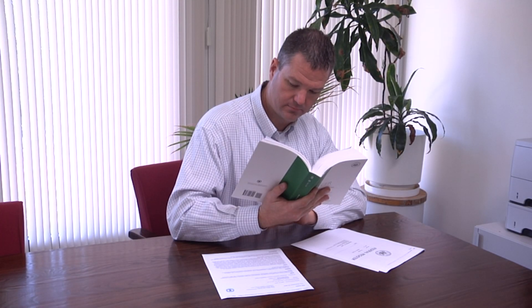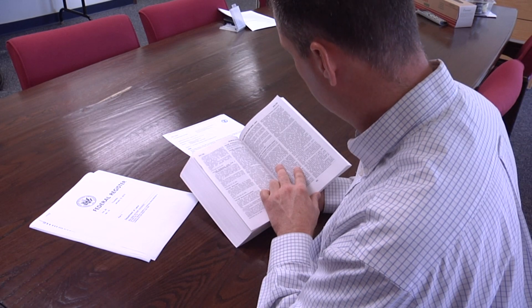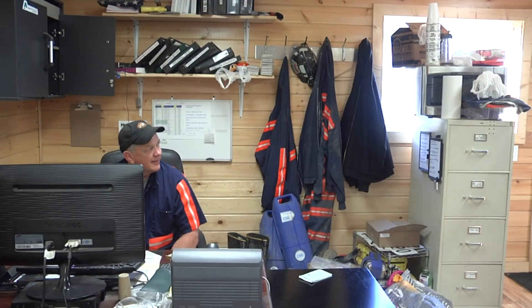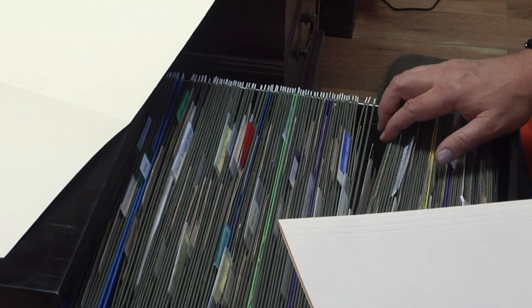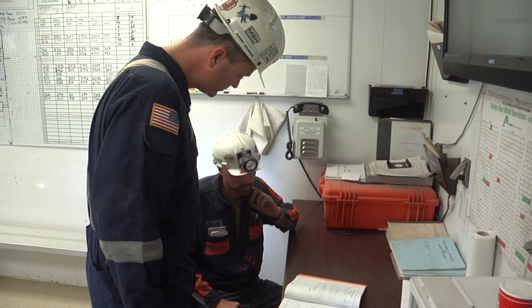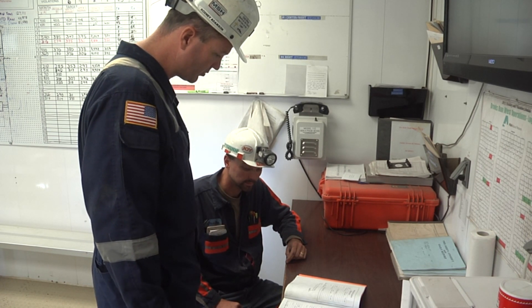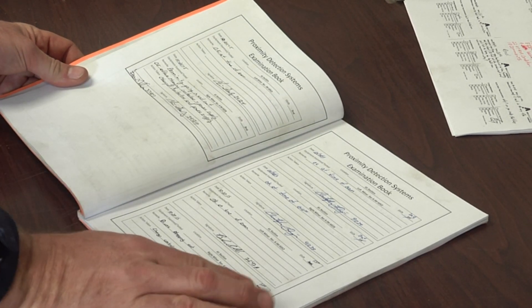When preparing for an inspection, review and understand 30 CFR 75.1732, policy and inspection procedures. Next, become familiar with the proximity detection system provisions. Conduct a records review at the mine site. These records must be maintained in a secure book or electronically in a secure computer system not susceptible to alteration. Review the mine records for any defects and corrective actions of machine-mounted and miner wearable components. These records provide a history of component defects or recurring maintenance of system components.